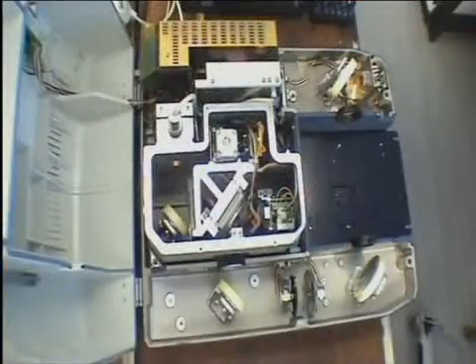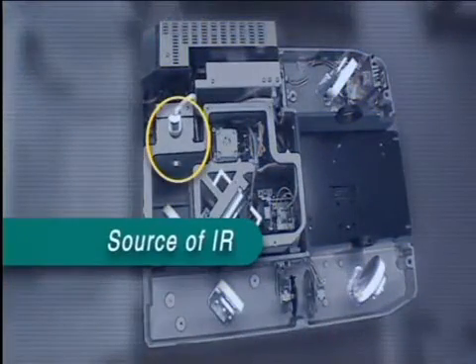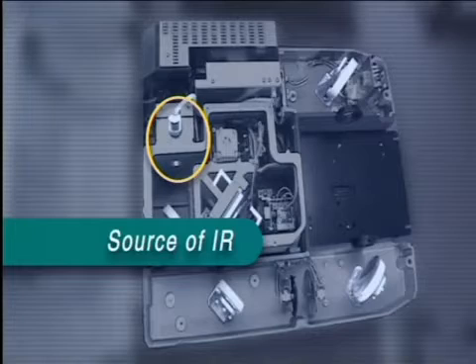All IR instruments have a source of IR radiation. This is a coil of wire surrounded by a ceramic capsule, which is heated electrically so that it gives out IR radiation. In other words, heat, over a whole range of frequencies.